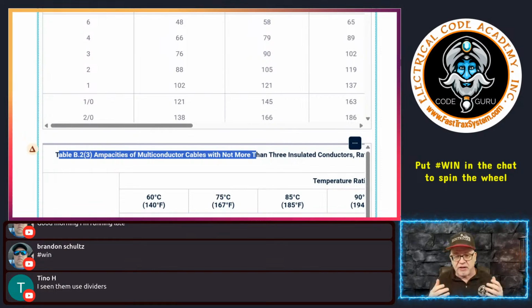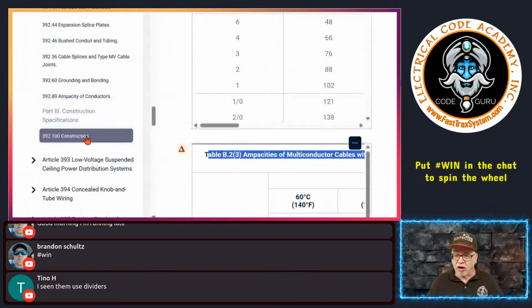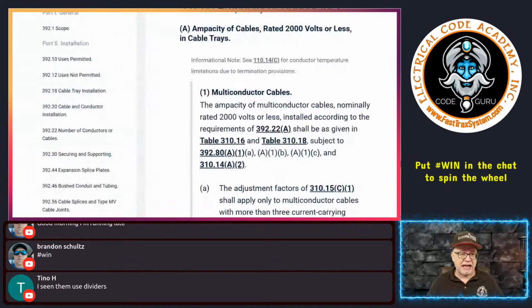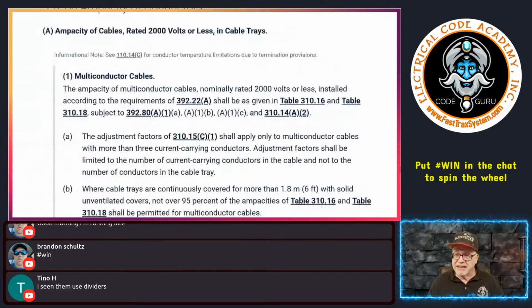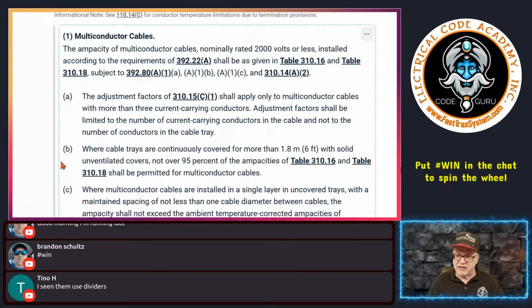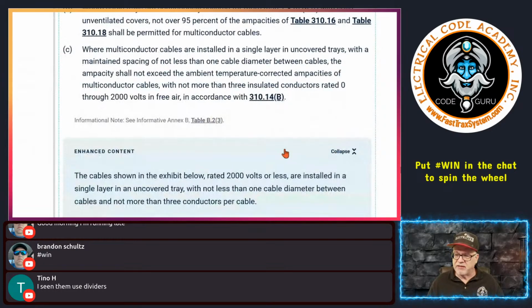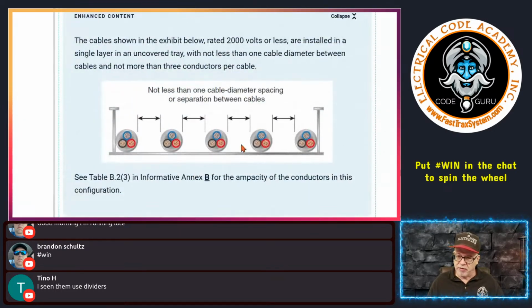Typically, they're going to use their own calculations in a software like ETAP or something like that. Most of the engineers that I know aren't going to touch that. Most of the engineers that I know are just going to base it on 310.16. But that's there for them to do this if they would like to. And you still have to meet the caveats of spacing. And that would be an example right here. So remember, the tray still has to be, we size the tray, right? In 392.22(A), right? And again, the tray has to be at least the width of the cable plus the space equal to a cable. If they do this, then the engineer can come up with their own ampacity values for these conductors, and it may get them out of a bind, but they're responsible for it.